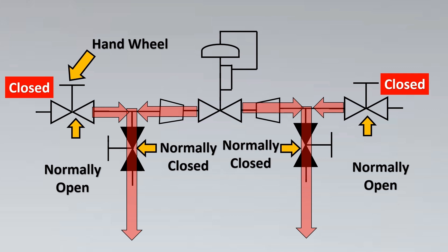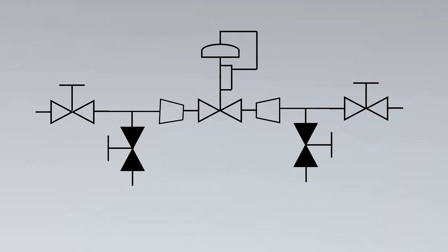So usually this NONC configuration is used for isolations, and sometimes neither the valves are colored nor entire statement is mentioned. In those cases you might find near the valve these words like NONC mentioned. So NO stands for normally open and NC stands for normally closed valve.